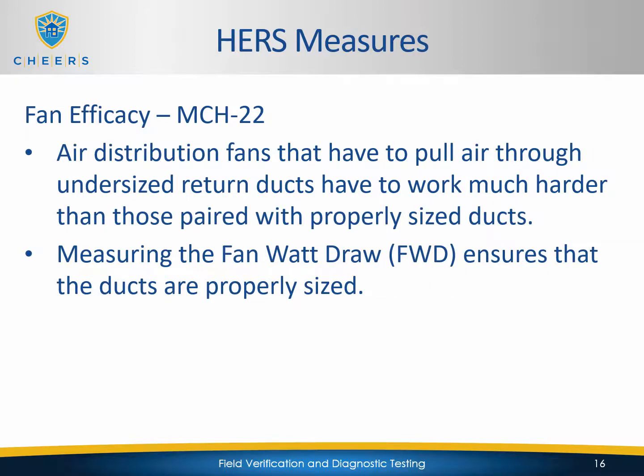Fan efficacy is going to be on the MCH-22. Air distribution fans that have to pull air through undersized return ducts have to work much harder than those paired with properly sized ducts. Measuring the fan watt draw, or FWD, ensures that the ducts are properly sized. So again, this deals with the duct system, and you'll have return ducts. This is where the air gets drawn from the house into the HVAC equipment, where it is then heated or cooled and then distributed out through the supply ducts.